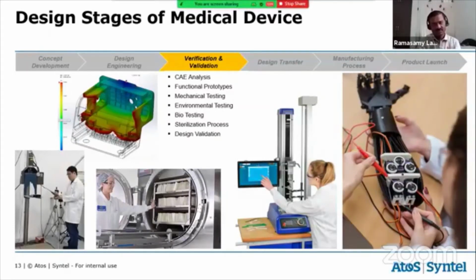At this stage we'll be doing verification and validation. What is verification and what is validation? Verification is checking the detailed design: it came out properly. We made a 10 mm square, so we check that the 10 mm square is there, and that it will take this much load. And if we drop a product from a 1 meter height, whether it withstands it. These kinds of activities are called verification testing.